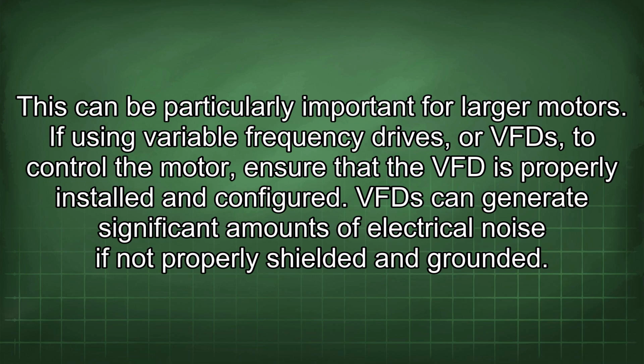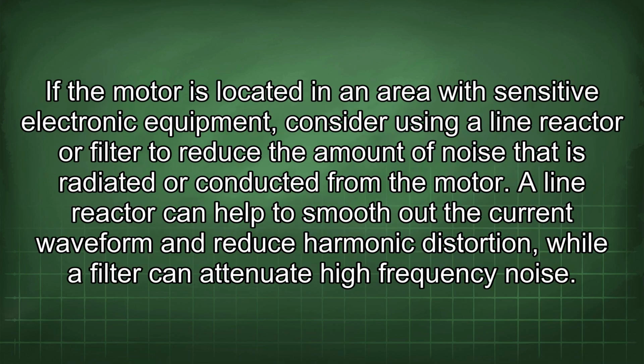If using variable frequency drives, or VFDs, to control the motor, ensure that the VFD is properly installed and configured. VFDs can generate significant amounts of electrical noise if not properly shielded and grounded. If the motor is located in an area with sensitive electronic equipment, consider using a line reactor or filter to reduce the amount of noise that is radiated or conducted from the motor.